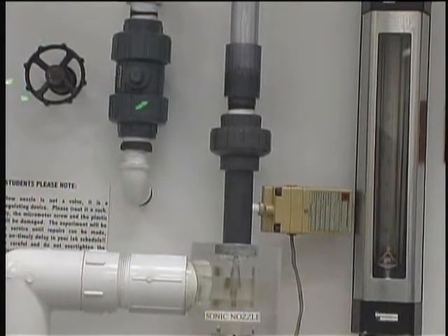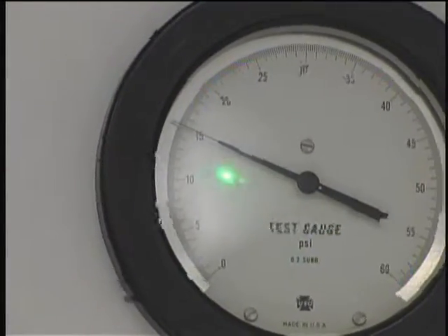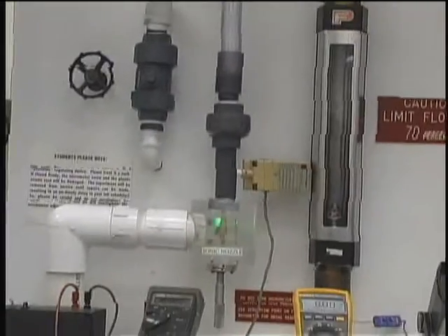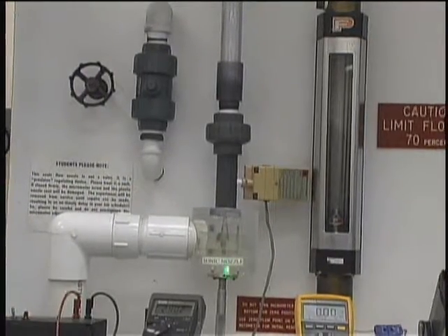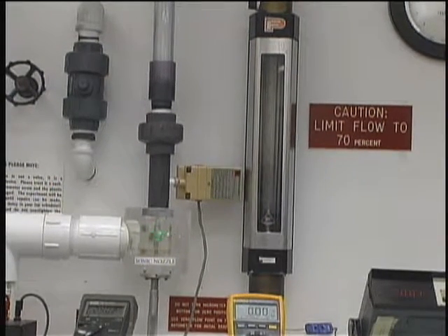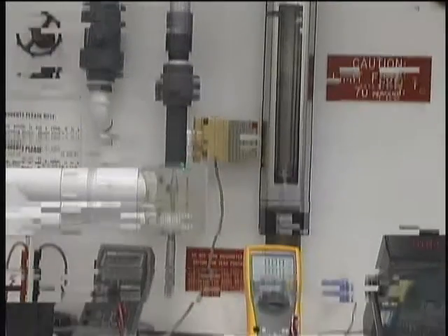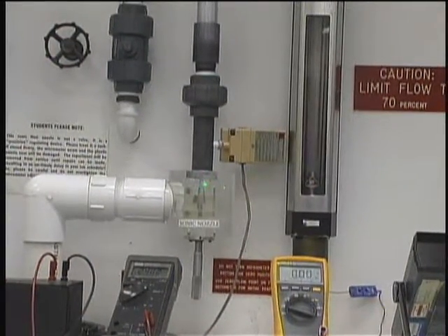Before I go to this point, the pressure here is obtained with a Bourdon type test gauge, as you can see, where we can read off the pressure immediately right there. And then once the air is allowed in the system, the first device it will see is a sonic nozzle. If you zoom in, you would notice that I have a cone, and the cone angle here is about 8.8 degrees. Then I can push that cone against a fixed area in here. As I push it against the fixed area, I will constrict it. So I can constrict it more or open it more, as we'll see in a minute.